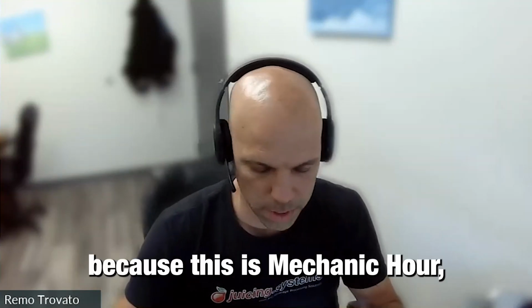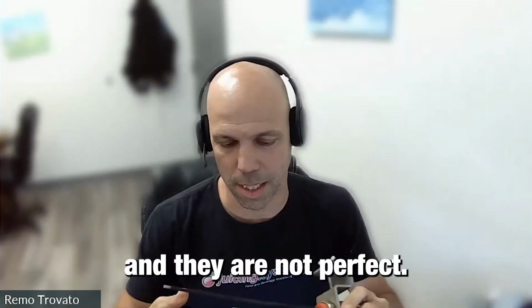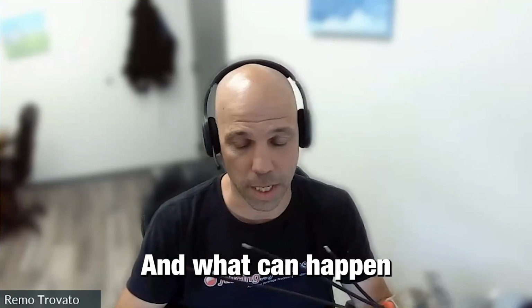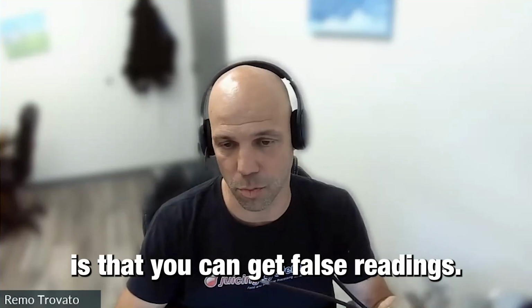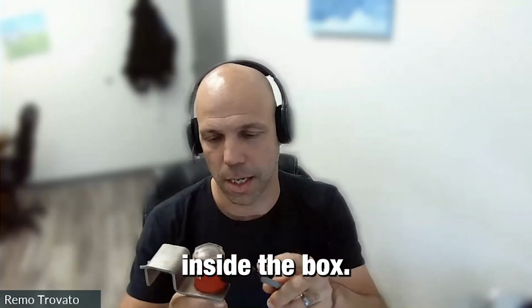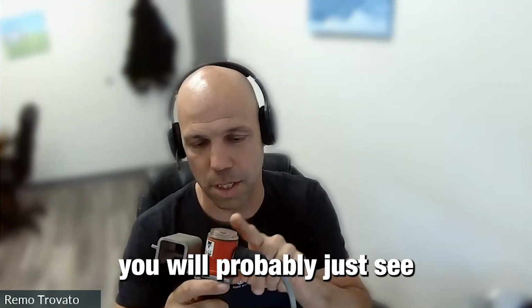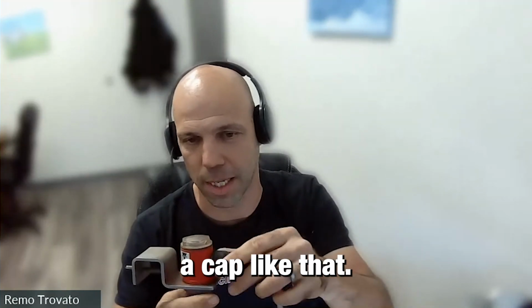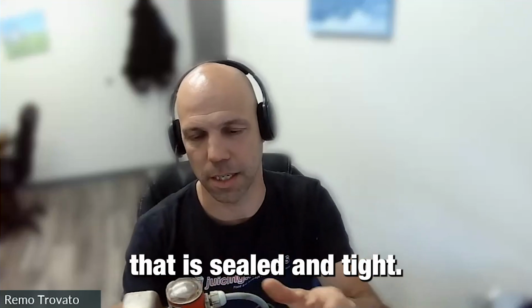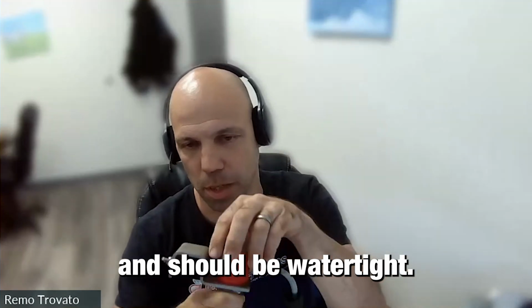Because this is Mechanic Hour, we want to look at what can happen with these things. They're not perfect. As we know, there's moisture everywhere, and what can happen is that you can get false readings. False readings happen when there's moisture inside the box. This is the new version. If you don't have that version, you would probably just see a cap like that. And this cap is actually a little fitting that is sealed and tight. So these are much better and should be watertight.